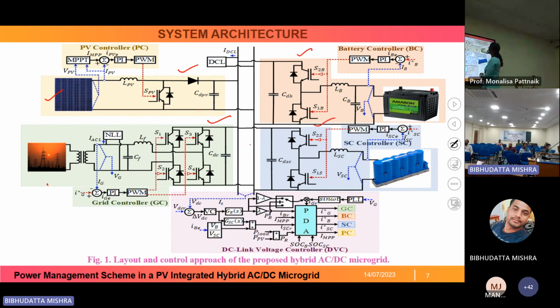This is the control algorithm where we have implemented the power management scheme to generate the reference current for these units. In the boost converter, the switching is controlled by the MPPT technique. In case of a grid-connected system, we always run the PV at maximum power point.